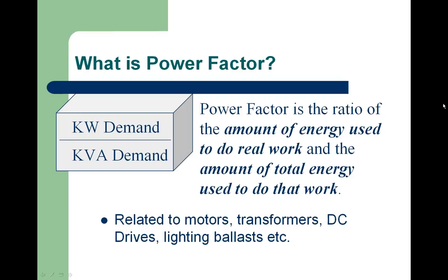A number of other things require magnetizing energy, which is kVARs. I said motors, and transformers also set up a field, so there are VARs required for transformers. DC drives typically have a very low power factor, generally in the 60s. Lighting ballasts, depending on the make, the newer electronic ones, typically have a very high power factor. And variable frequency drives have improved over the years, and they also have a relatively higher power factor.